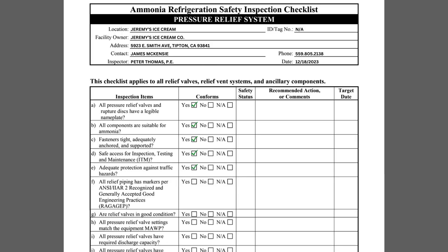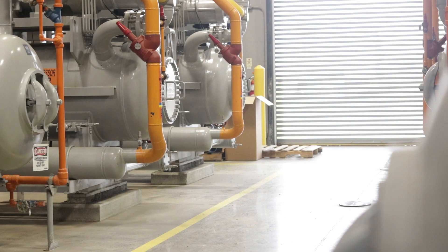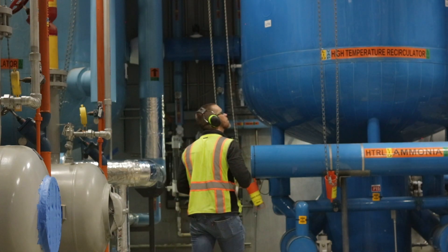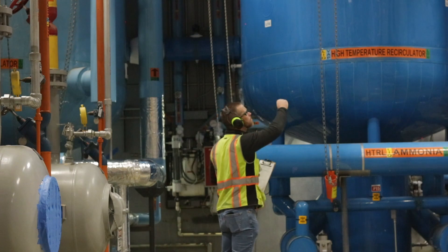Item E asks if there is adequate protection against traffic hazards. Pressure relief valves can be located throughout the facility, and it's imperative these valves are adequately protected from potential impacts from forklifts, aerial lifts, or service trucks. Machinery rooms often protect many of the pressure relief valves from this contact.